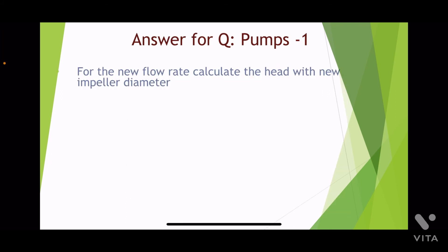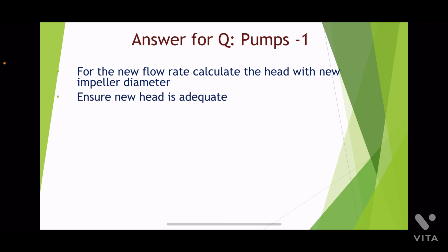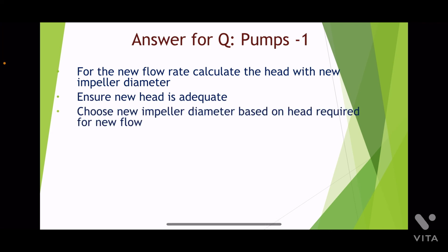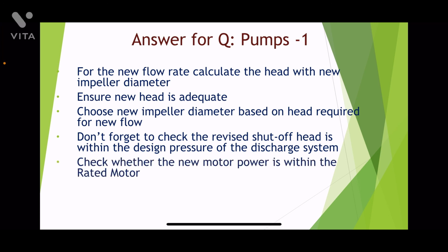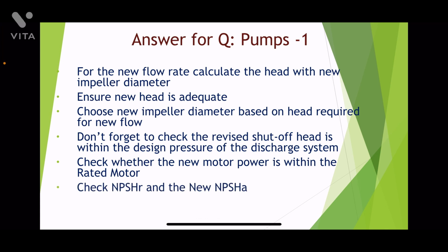The idea is: first, for the new flow rate, calculate the head with the new impeller diameter. Ensure that the new head is adequate. Choose the new impeller diameter based on the head required for the new flow. Don't forget to check that the revised shutoff head is within the design pressure of the discharge system. Check whether the new motor power is within the rated motor power. Also check the new NPSH-R and the new NPSH available.